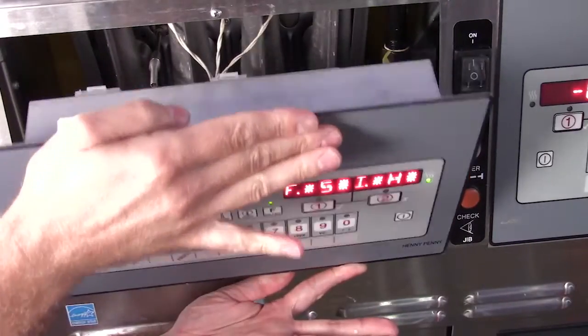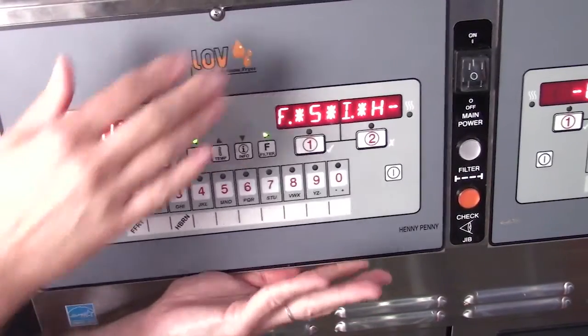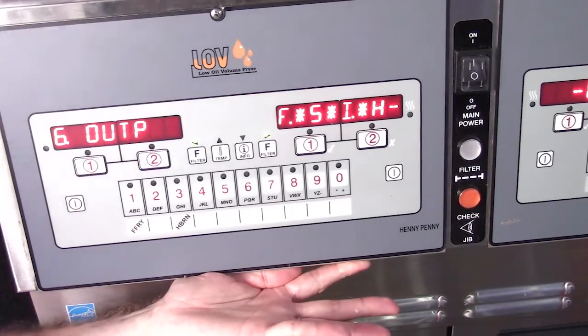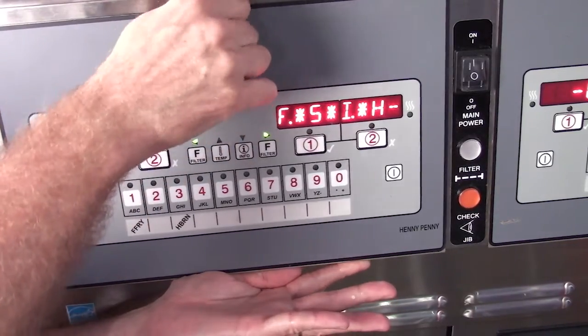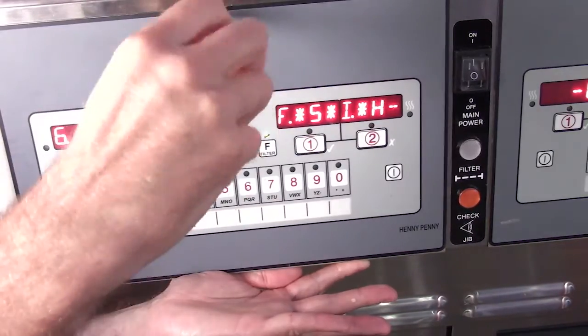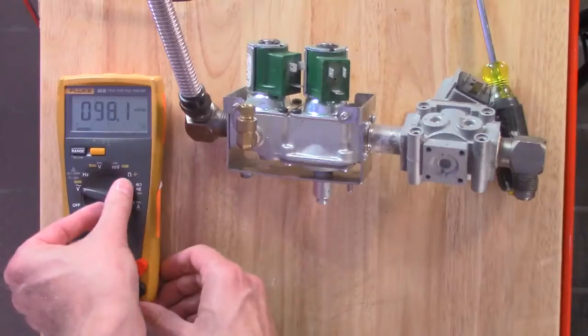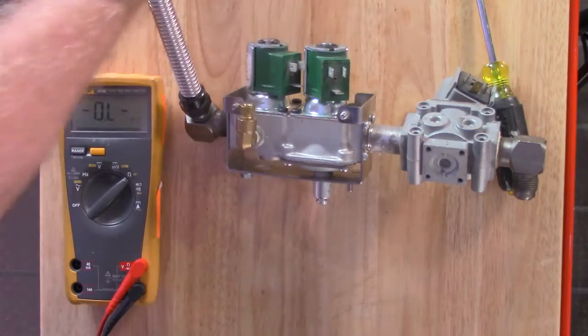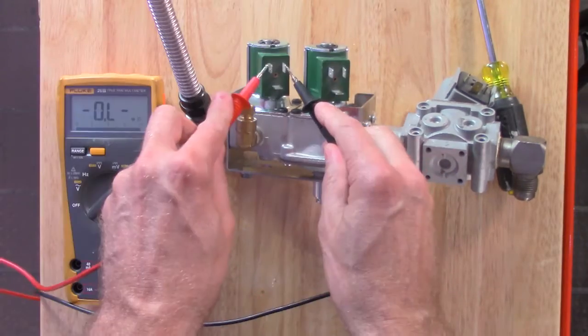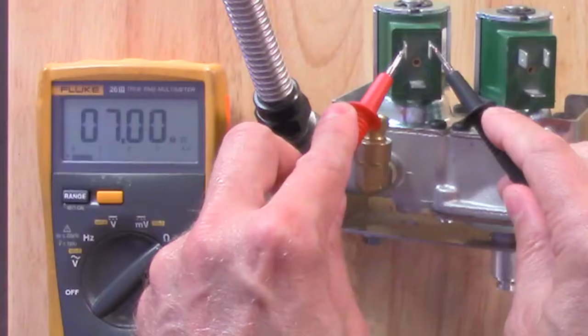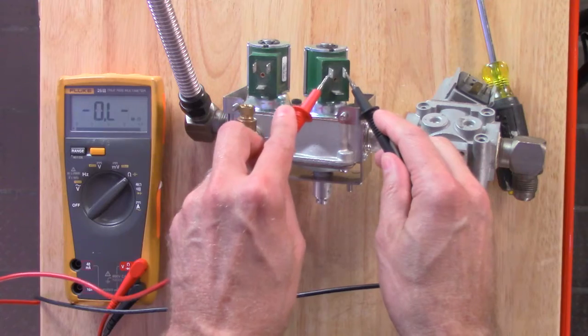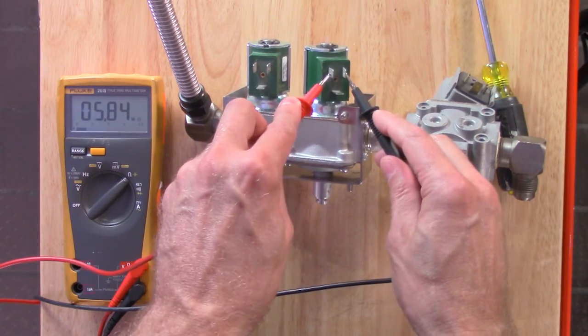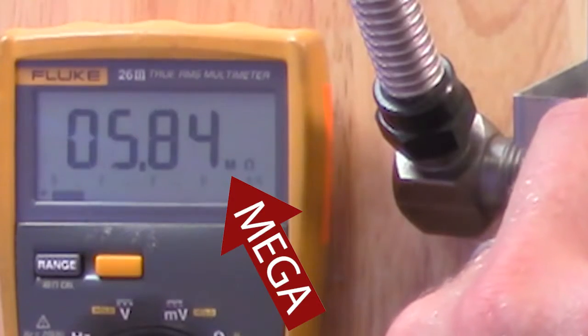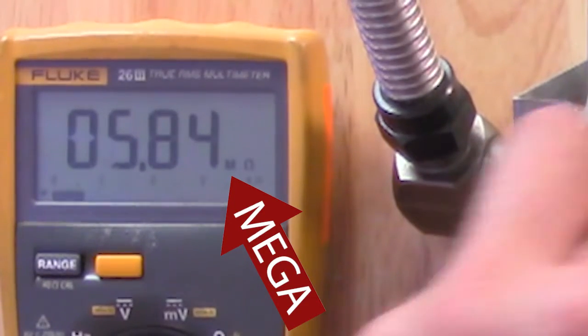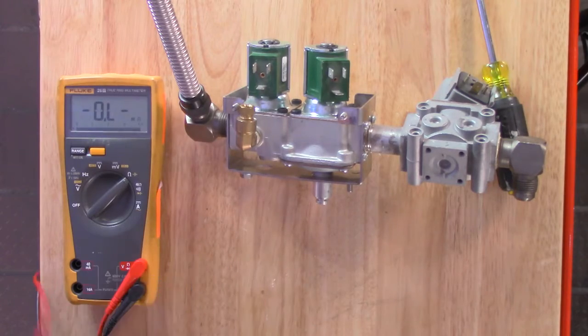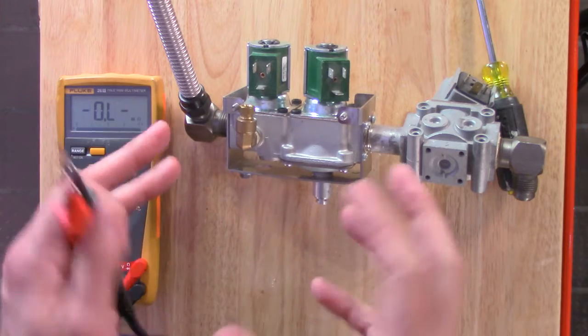Got my hand everything, hinge it, get here, drop it down, push up. And then I'm going to go ahead and tighten this up. Put our voltmeter to ohms, and we can ohm it out, do comparative. So right here is for our main burn. It's right at 7. We go over here, then check for our pilot. It's right around 5.8. So they're comparative, they're fine.